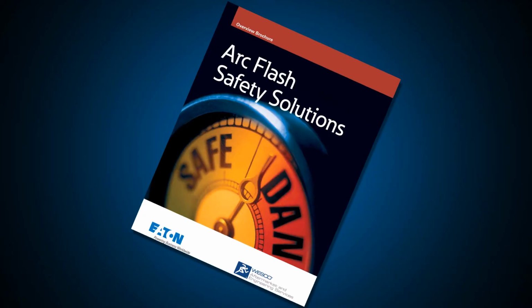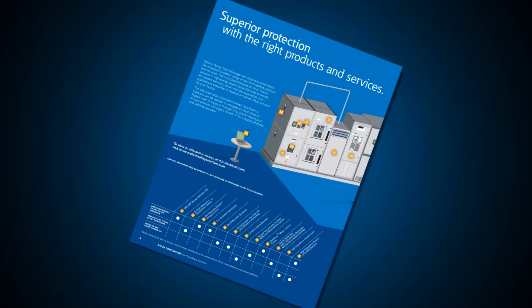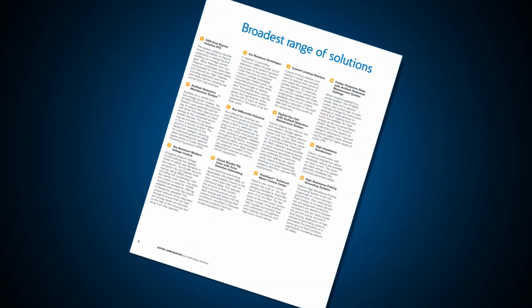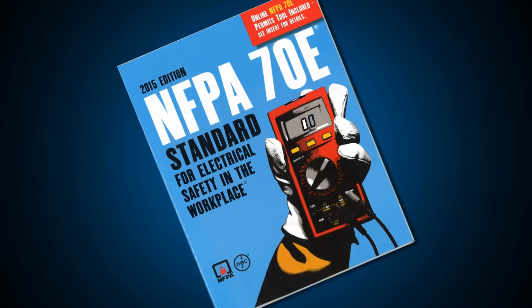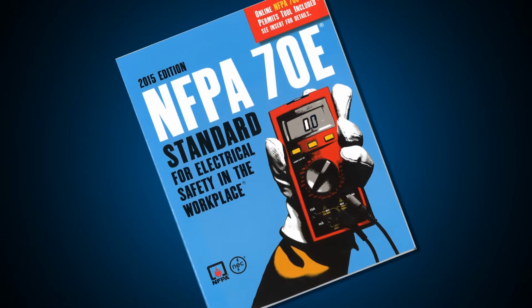These labels are created by our Power Systems Engineering Group, using models of electrical power distribution equipment data from your site with the sizes and settings of your protective equipment taken into account. This ensures that the calculated arc flash levels are accurate for your situation. Our PSE group has done thousands of arc flash studies and applied solutions for our customers' facilities and our own. The NFPA 70E standard serves as a guide defining the method that companies should use to perform arc flash analysis, labeling, and training of personnel.